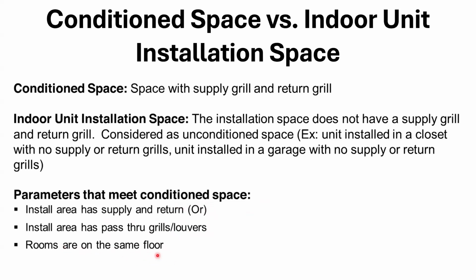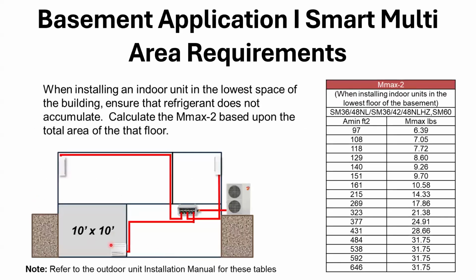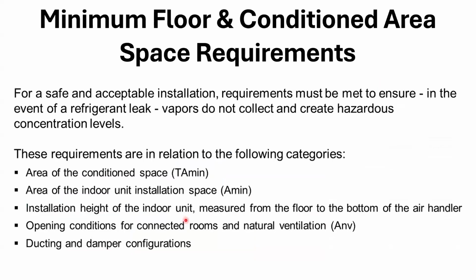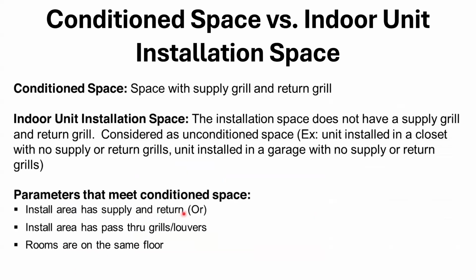Rooms on the same floor. This was brought up too. What if this is in the basement, an SVZ air handler, and they have stairs that go up to the living room? Can you count the living room? It's in the install manual. I had to look it up and found it. You can't count the stairs and the living room. That doesn't count. So you've got to stick with the room downstairs where the unit is located. You can't, because the stairs are open to the upstairs living room. That's not a transfer that they're allowing. So that's what they mean by rooms on the same floor.